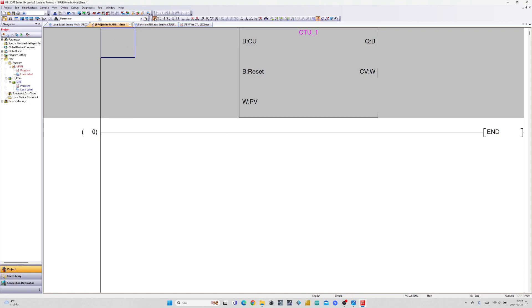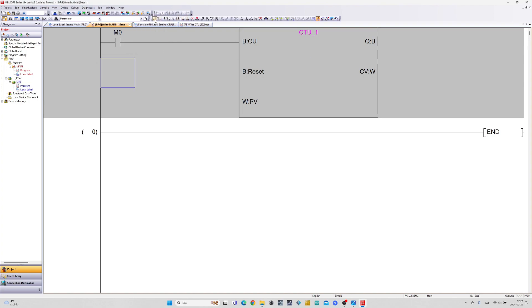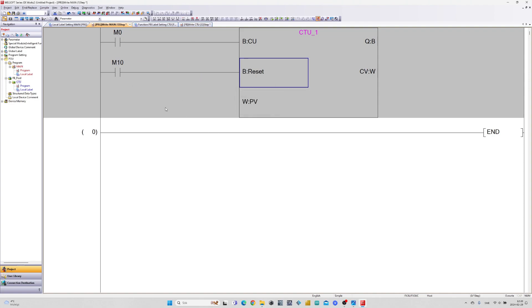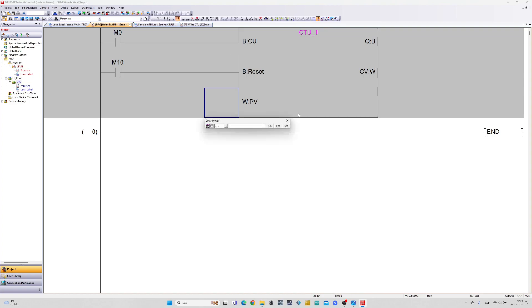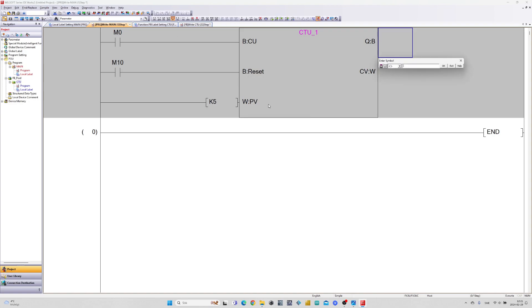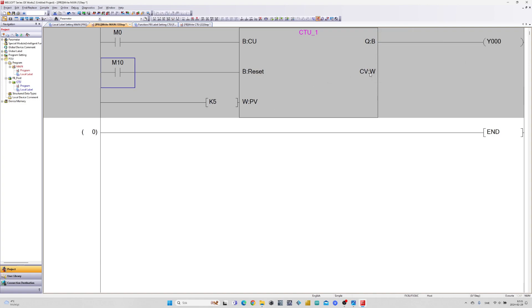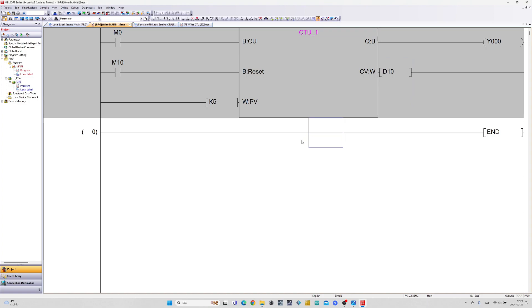I will add a memory bit to my count up and reset input, and to my preset value input an application instruction with a value for how much the block should count up to. On the output I will use Y0 from my PLC, and on CV I will just add a tag that can keep track of the counted value.